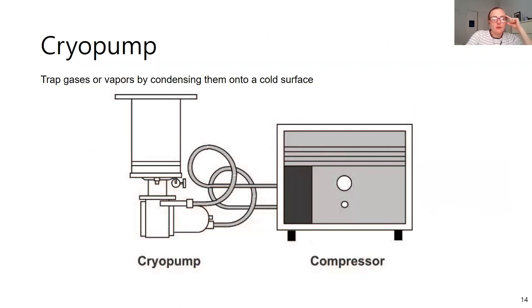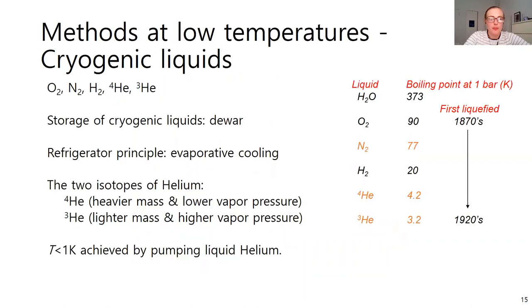Finally, an ultra high vacuum technique that I know is in Professor Gal's lab and Professor Rule's lab is using a cryo pump. You'll see those signs that say like the coldest place in Cleveland because they're using liquid helium. This is by bringing the temperature of your pump down so low that the gas molecules and the water vapor, helium, hydrogen, or the hydrogen, the nitrogen, the argon that's in the atmosphere will actually condense onto a surface because they're so cold. So they're actually entering the liquid phase instead of being in the gas phase and that removes them from your system.